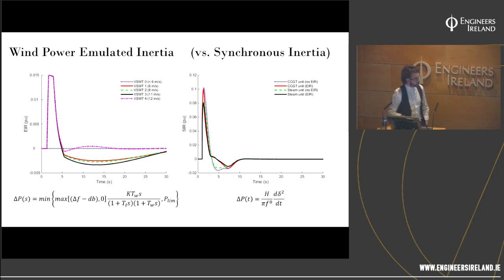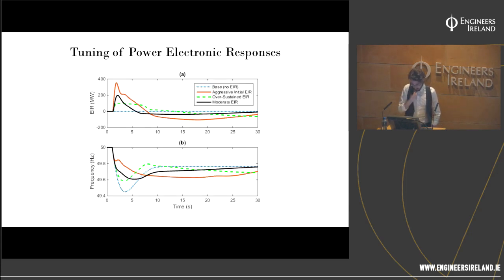Whatever the grid is, that's more or less what you're going to get. And just to hammer the point home, this is the equation that describes the inertial response, or the power injection, of a conventional generator. I don't want you to get worried about it. This is the equation that describes how you control a wind turbine to emulate a somewhat similar inertial response. But because you can tune this, you have the keys, in a sense: you can't change this, but you can tune these parameters to meet your system needs, albeit slower than the synchronous inertial response. Because it's a controlled response, it'll do what you tell it to do, and as a result you need to be very careful with how you set those parameters.